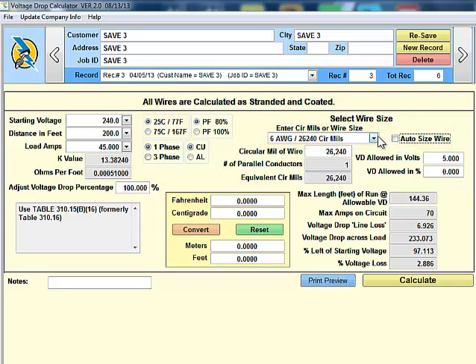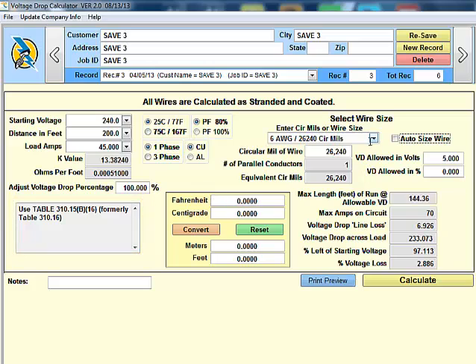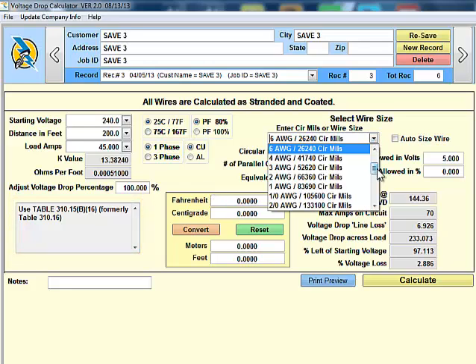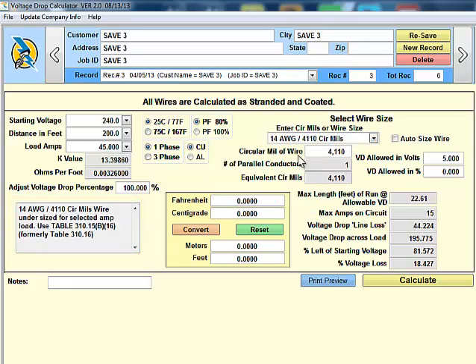If I deselect the auto wire size, notice what happens is we have a note pops up that we have to pay attention to 310.15(B)(16) to get the wire size. Let's go ahead and drop it down to a 14 gauge and see what happens. The note points out that 14 wire gauge is undersized for the selected amperage.